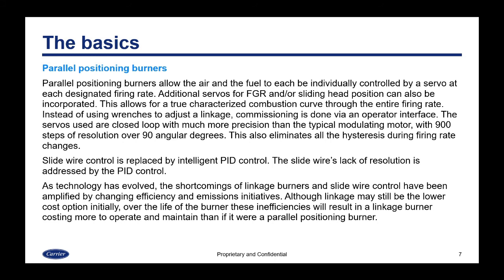As technology has evolved, the shortcomings of linkage burners and slide wire control have been amplified by the changing efficiency and emissions initiatives. Although linkage may still be the lower cost option initially, over the life of the burner, these inefficiencies will result in a linkage burner probably costing more to operate and maintain than if it were parallel positioning to start with.